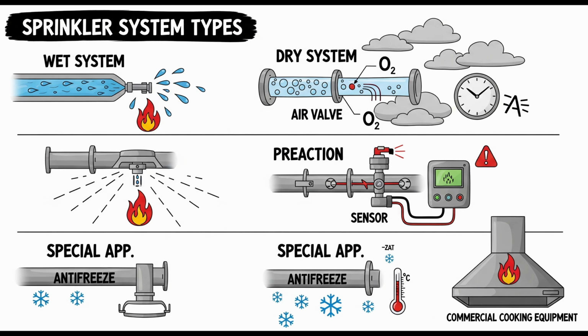Strainers are required in the riser or feed main for sprinklers with K factors smaller than K2.8. Yes, same reason as we saw in kitchen systems. Smaller K-factor sprinklers have smaller orifices, making them more prone to clogging from any small debris that might be in the water supply. Strainers protect these smaller openings. Okay. A pressure gauge is required immediately below the control valve of each system.